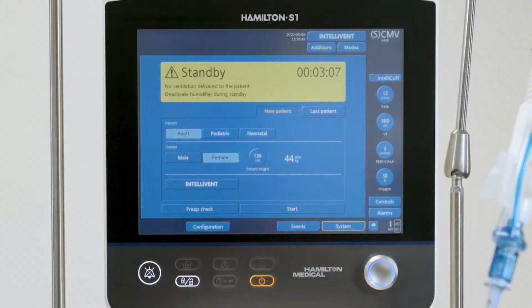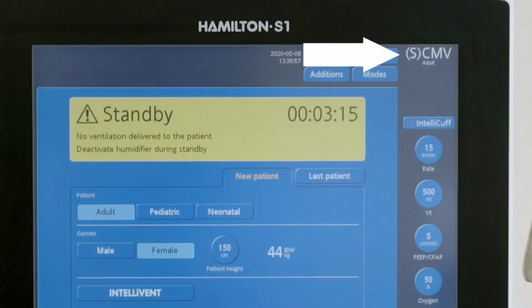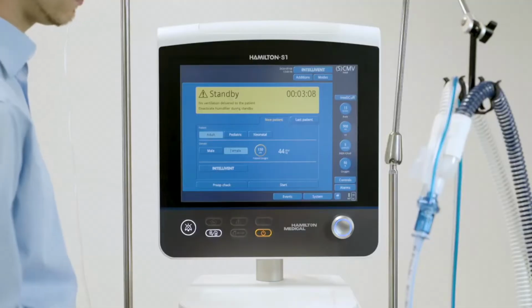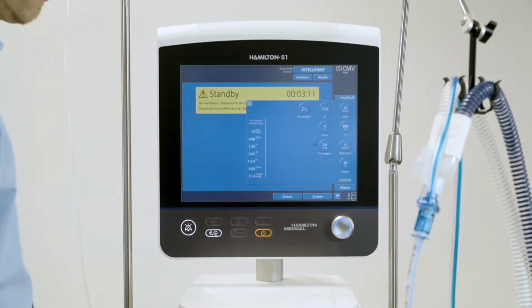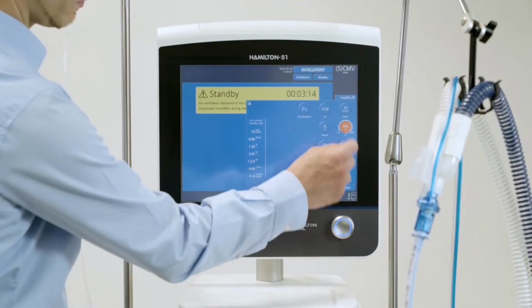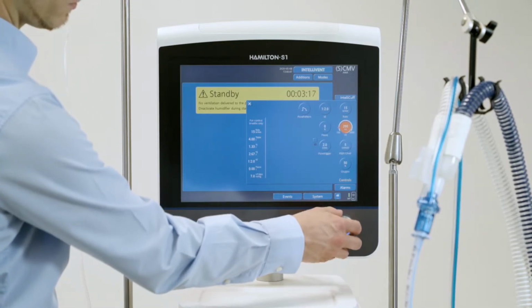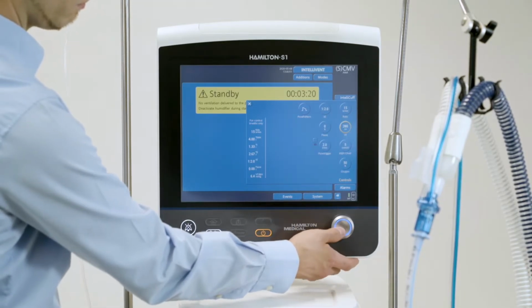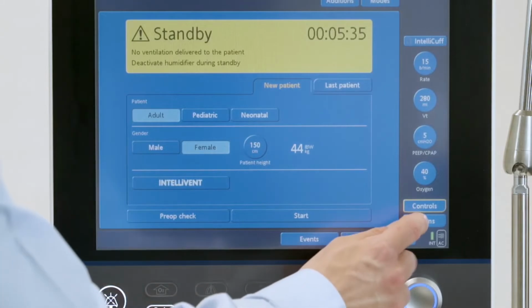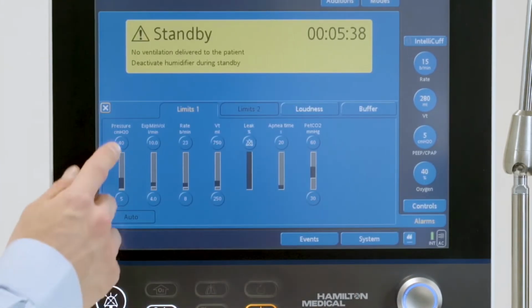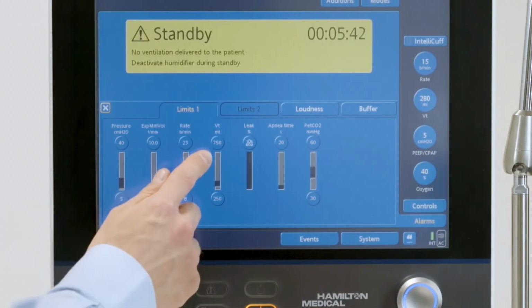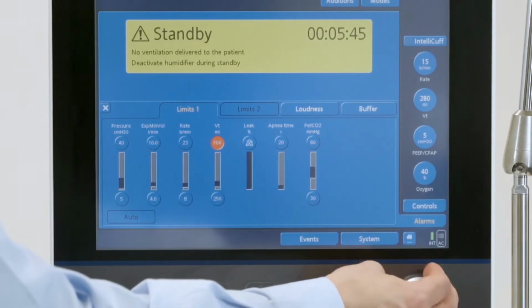To start ventilation quickly for a new patient, you can use a default ventilation mode with all the settings pre-configured. The default mode, together with a selected patient group, is displayed in the upper right corner. Touch Controls to review and adjust the control settings. To review and adjust the alarms, touch the Alarms button. Then, touch the alarm control and adjust it.